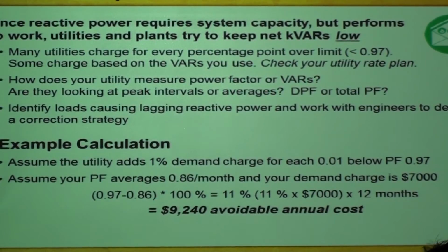So, the example of calculation: if you assume that the utility is adding 1% demand charge for every 0.01 below the 0.97, and if your power factor is averaging 0.86 per month, your demand charge is $7,000 on a monthly basis. So again, if you look at the difference, times 100%, again times 12 months, you're looking at an annual cost of almost $10,000 just on wasted power factor. Just on reactive power, so that's a big cost. Now, you might not see this in your bill today, but it's an easy calculation to do. To do that, the only thing you need is tools to measure, to quantify, okay?